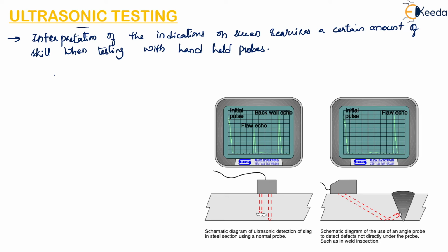So the trigger level of this signal is variable, and it can be made to operate a variety of mechanical gates and flaw warnings. Furthermore, improvements in computer technology allow the test data and the results to be displayed and outputted in a wide variety of formats. So this technique can be automated, and with the help of a computer, the results can be displayed in different formats.